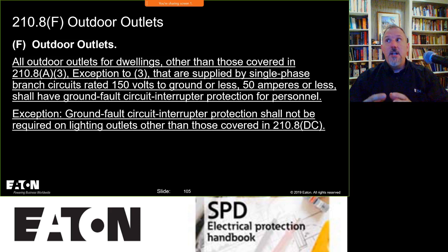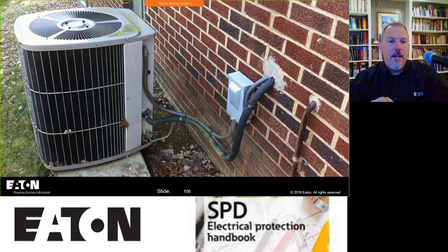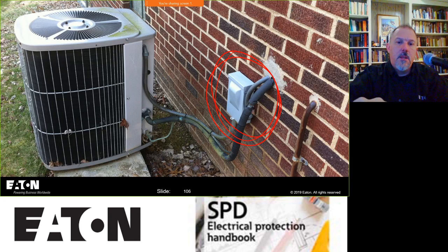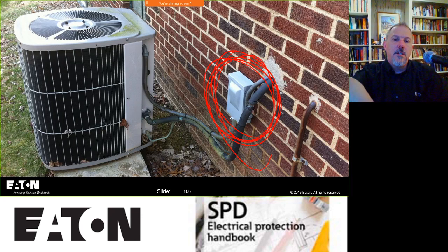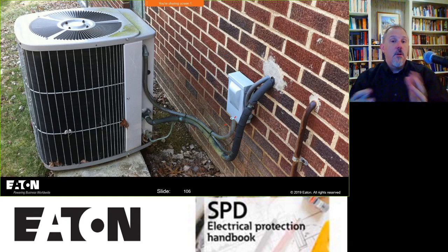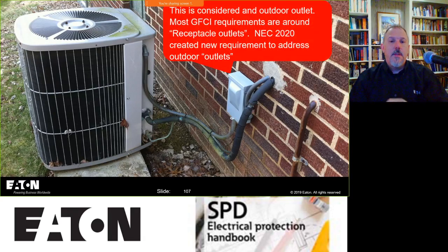Now, this is a considerable change. Outdoor outlets, all outdoor outlets for dwellings other than those covered in A3, exception 3, that are supplied by a single phase branch circuit rated 150 volts to ground or less, 50 amps or less, shall have ground fault protection. The key here is there's an exception for lighting outlets, so you don't have to worry about those. But remember, we're talking about an outlet - like that disconnect you put there for AC, that is your outlet, and that's going to have GFCI protection regardless, 50 amps or less. This applies since it's not a 210.8A or B - this is dwelling units, and it's an outlet, not a receptacle.